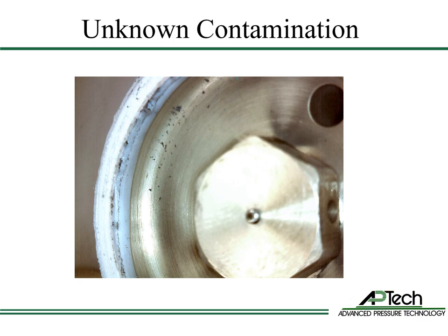This image shows dark particulate contamination on the low pressure side of a regulator. Often the chemical composition of the particulate matter is difficult to identify. Even with extensive lab analysis, the identity of the contaminants is generally inconclusive.